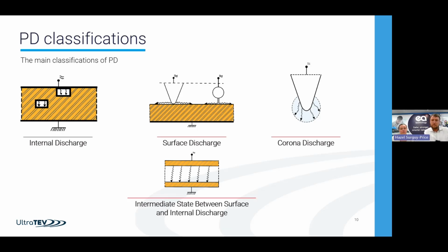Broadly, there are three main categories of PD, and depending where your switchgear is, you might care more or less about some of these. First, internal discharge, that's happening inside the insulation. That's very much like the CT on the last picture. These air voids and impurities concentrate the stress and cause that breakdown, which then creates a void within the insulation. It's hard to see, hard to identify from the outside, and usually requires a reasonable amount of intervention to address.